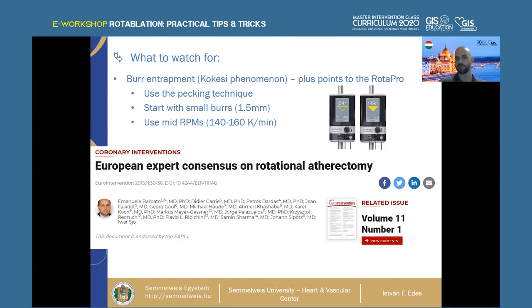When the RPM drops between 1,000 to 5,000 RPMs, you get a hollow yellow square right there, and it's absolutely visible when you're doing the atherectomy. If it falls more than 5,000 RPMs, you get a yellow square and a warning sign that a stall is imminent and not to over-push your burr. This is extremely helpful, and one of the new things on the device that has helped my everyday practice a lot.